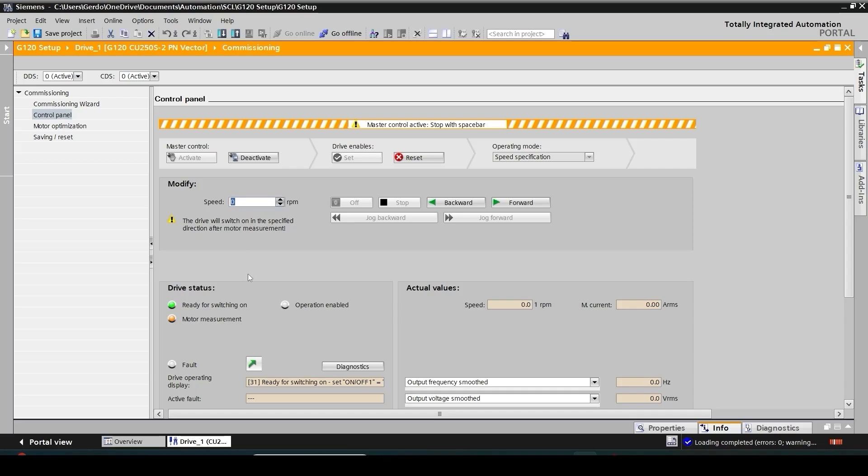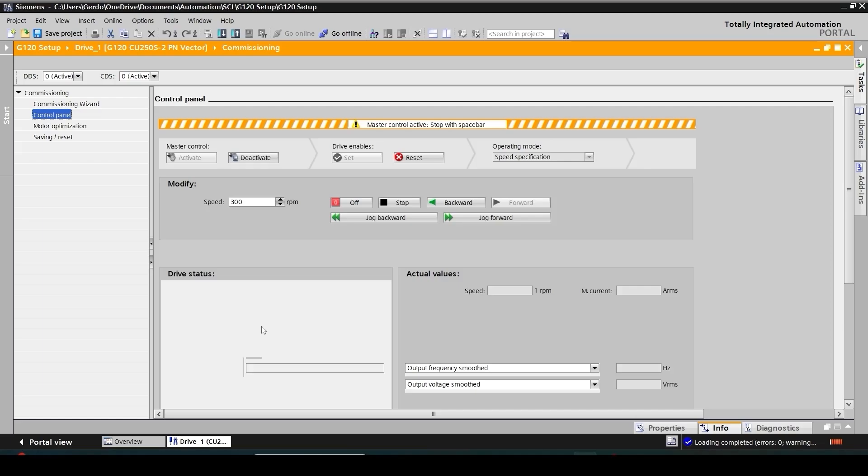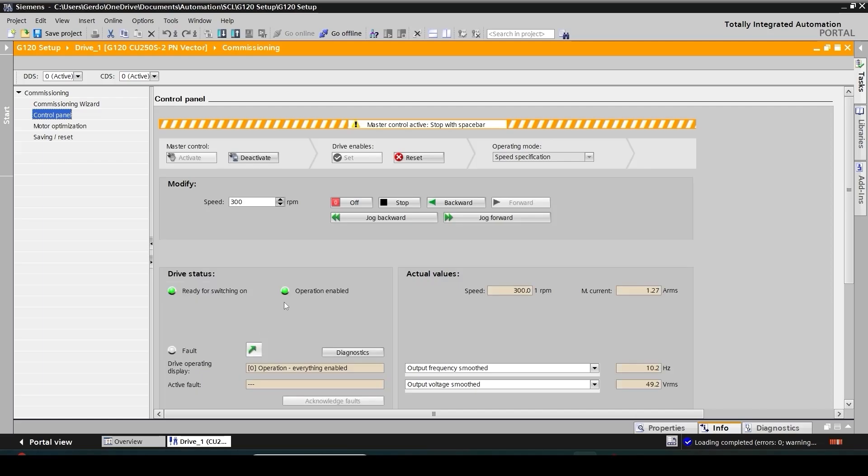I just need to specify some speed setpoint. So I go with like 300 RPM and then click either on forward or backward and then watch my motor if it's rotating or not. I can hear the sound of motor. It's doing some measurement, stationary measurement in process. And after that the motor is in operation and I can see the speed of 300. I'm able to stop the rotation.